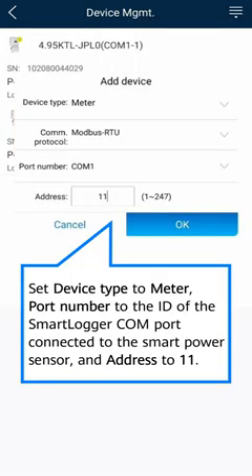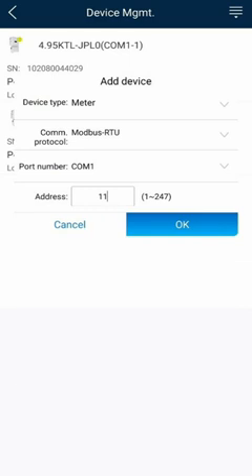Set Device Type to Meter, Port Number to the ID of the smart logger COM port connected to the smart power sensor, and address to 11.